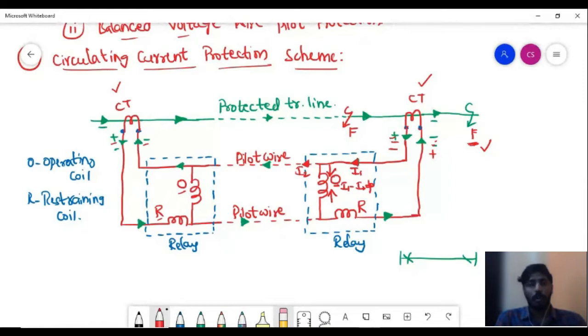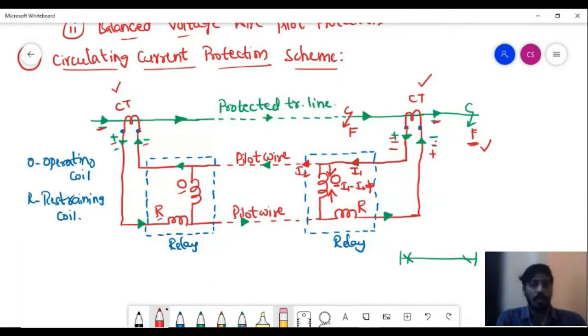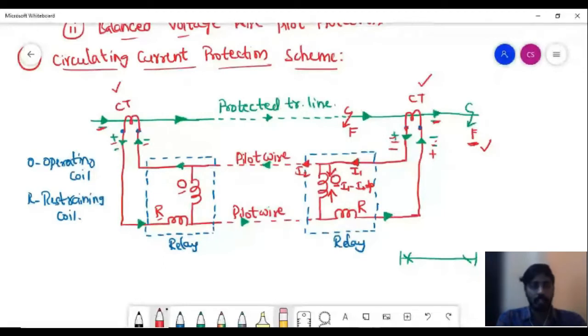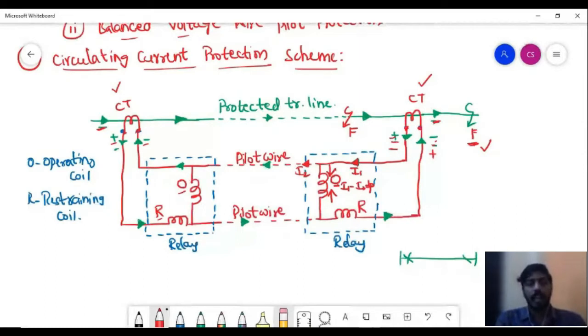Under normal operating conditions, there is no current flowing through the operating coil because the current at the sending end and the receiving end are the same — there is no fault. Whatever the CT at the starting point measures, the CT at the ending point will also measure the same amount of current. There will be no difference in currents, so there is no chance for current to flow through the operating coil.